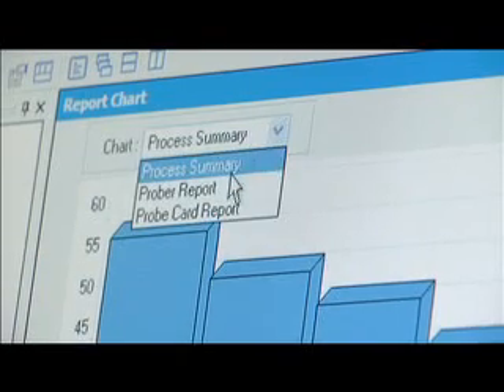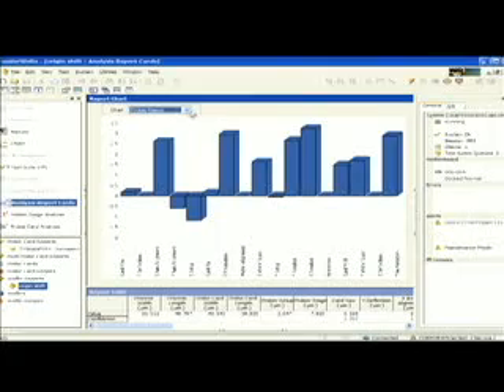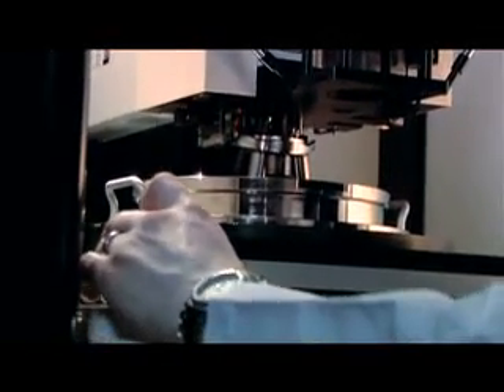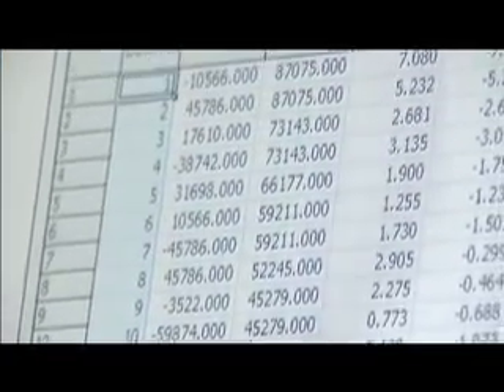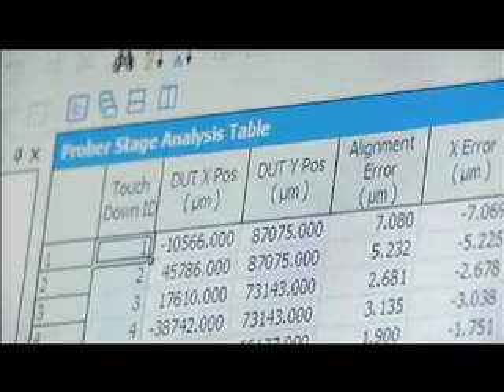The waferWorx 300 delivers reports on the performance of the test cell in a descriptive format that enables the operator to quickly determine those parameters with the most adverse effect on the process and take associated corrective actions. In minutes, the waferWorx 300 will analyze your stage, probe card, and prober performance, delivering critical data on the status of your process. And so that methodology of modeling that and isolating how your probe card is performing, how your probe stage is performing, how your setup's performing, and closing that loop back is a very critical component of understanding your probing process.